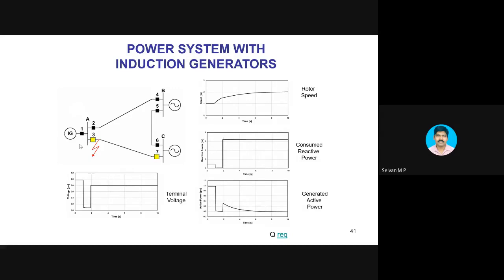So this happened because of a fault present in the system for, say, 0.4 to 0.6 seconds. Because of that, I have to switch off the wind turbine, and again I have to connect it. In the meantime, the power system will face a deficiency in real power too, because it was supplying 1 per unit of real power. Now that is lost. In number it may look small, 1 per unit, but in actual value that may be 100 megawatt, 200 megawatt, 300 megawatt, or even a 500 megawatt system. So that power loss will lead to other issues in the system.